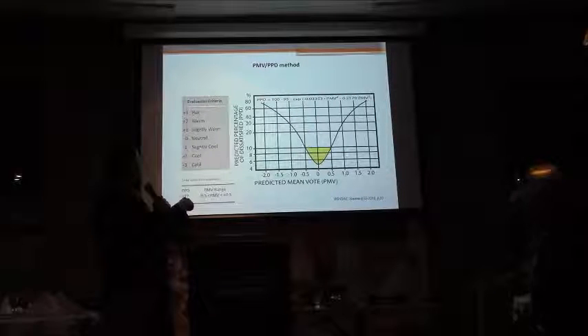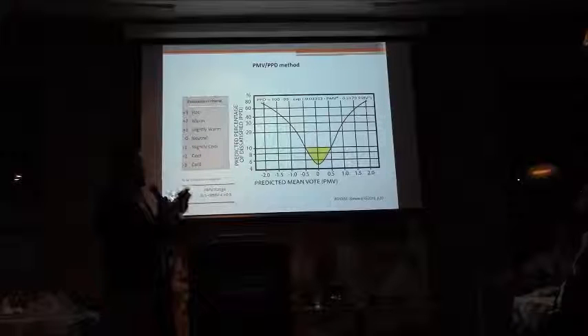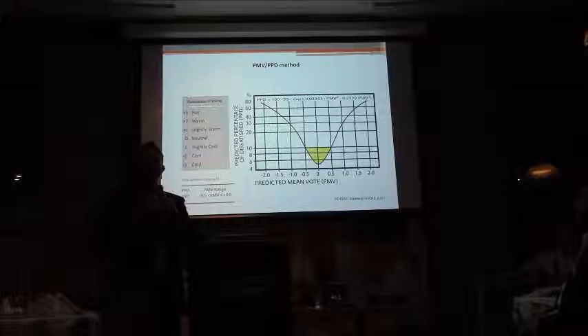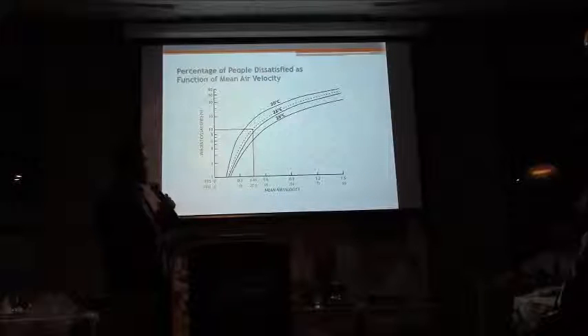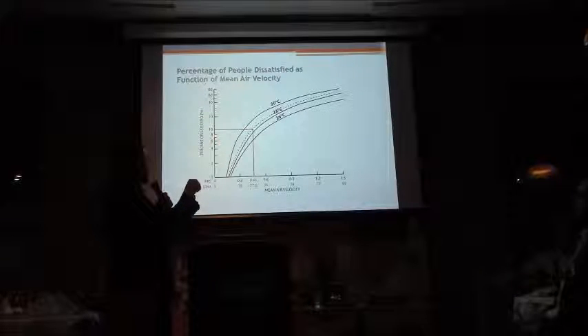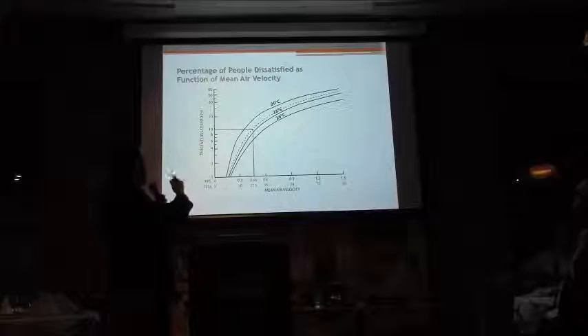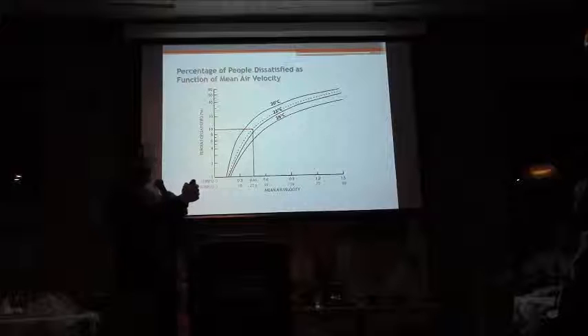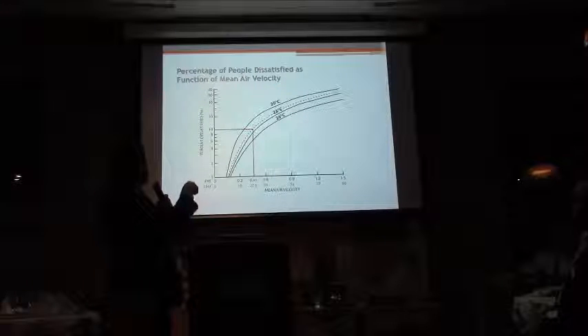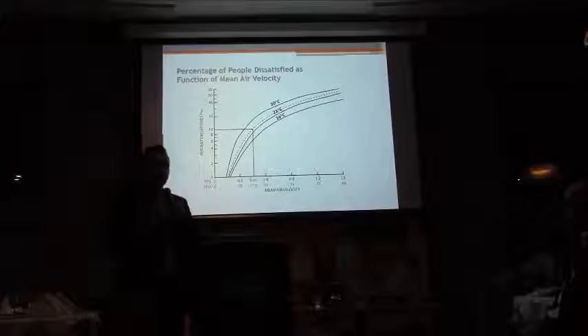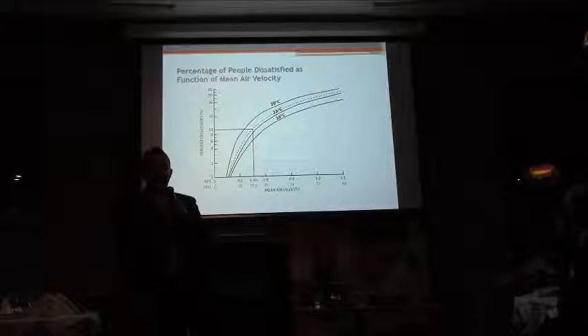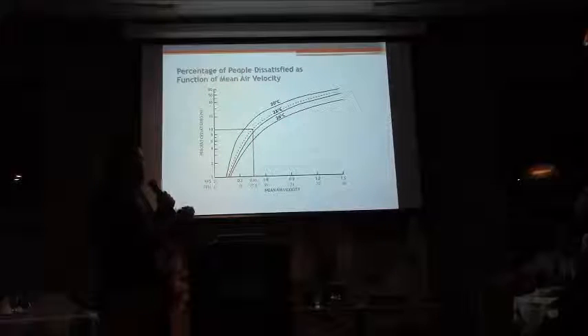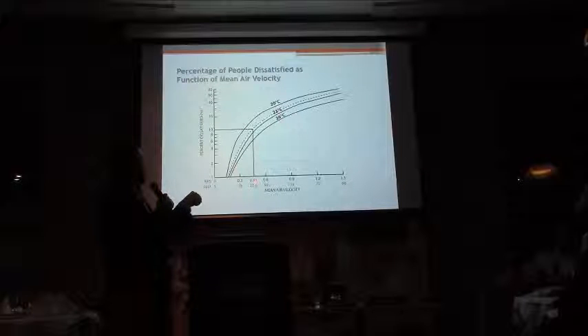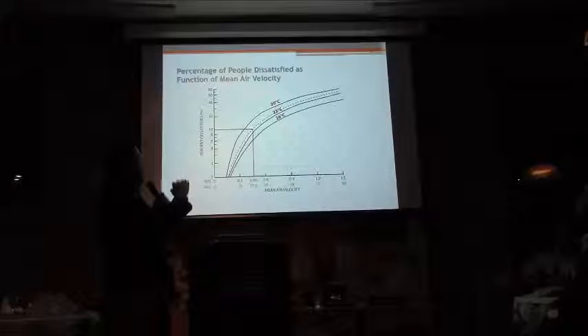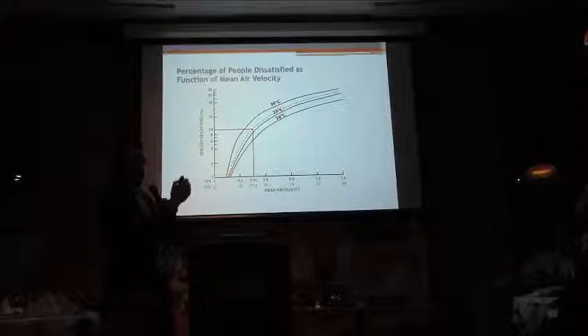So you want to be between -0.5 and +0.5 if your PPD is under 10%. That's the way they calculated it statistically. So on the next slide, like I said, the PPD has to be a maximum of 10. And this is a PPD versus air velocity graph that you can find in the ASHRAE 55 standard. If you look at it here, and you take a temperature of approximately 22.5 degrees Celsius, that's around 72.5 degrees Fahrenheit, which is a common design temperature, I believe. You want to have a maximum velocity of 27.6 feet per minute, as defined by ASHRAE. So we can round that up to 30.